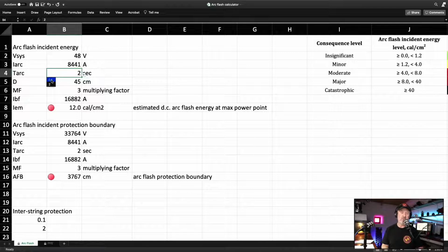So watch what happens when I put in string overcurrent protection. I drop down to 0.6. I get a green light. It makes a huge difference having that interstring overcurrent protection. So I'm still pretty high here in terms of the arc flash boundary, but it's really reduced my arc flash incident energy a lot.